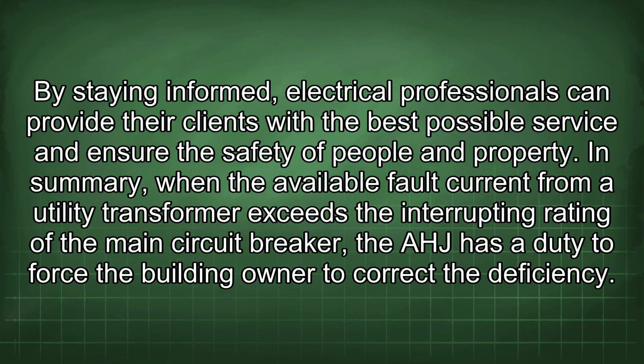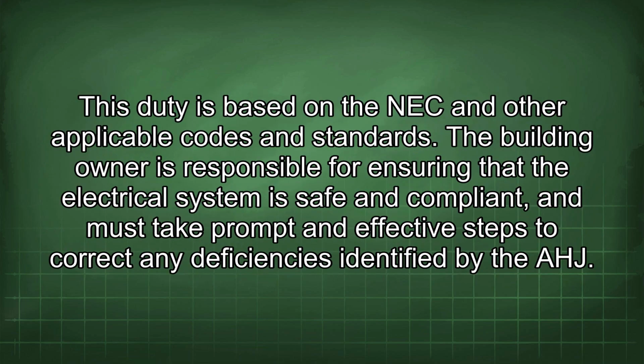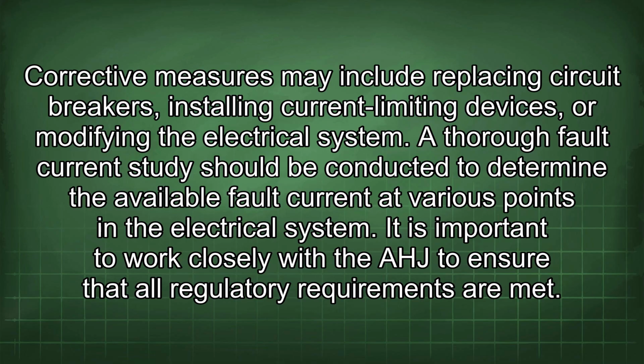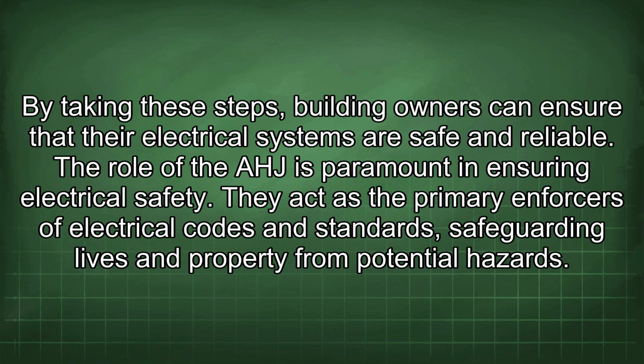people and property. In summary, when the available fault current from a utility transformer exceeds the interrupting rating of the main circuit breaker, the AHJ has a duty to force the building owner to correct the deficiency. This duty is based on the NEC and other applicable codes and standards. The building owner is responsible for ensuring that the electrical system is safe and compliant and must take prompt and effective steps to correct any deficiencies identified by the AHJ. Corrective measures may include replacing circuit breakers, installing current limiting devices, or modifying the electrical system. A thorough fault current study should be conducted to determine the available fault current at various points in the electrical system. It is important to work closely with the AHJ to ensure that all regulatory requirements are met. By taking these steps, building owners can ensure that their electrical systems are safe and reliable.